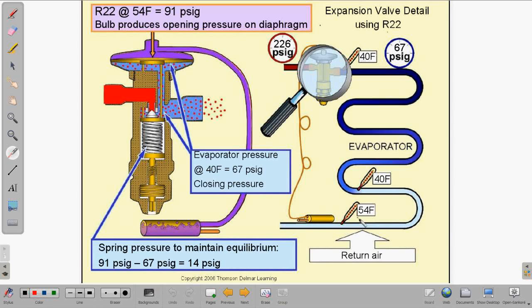The same thing happens if the bulb is reattached and this goes up. Someone opens the door in the home, and the sliding glass door is open. It's 90 degrees outside. We start to get more heat load. What will happen is the outlet temperature right here is going to start to go up. So when the outlet temperature goes up, the bulb pressure increases, pushes down on the top of the diaphragm, and allows more refrigerant in to maintain proper superheat and to adjust for any varying cooling loads. And the same thing happens in reverse. If it starts to get into the evening time, the outlet temperature starts to drop here, the bulb pressure decreases, and then it has less opening force and closes just a bit more and maintains superheat.